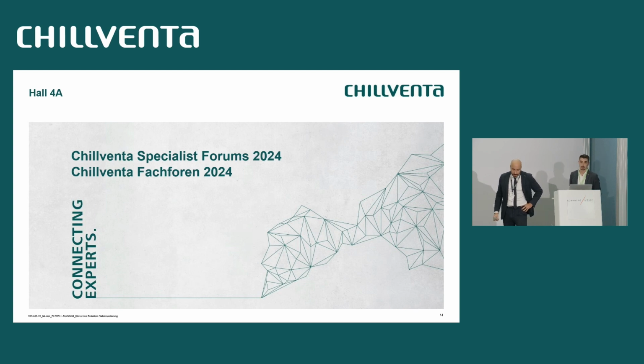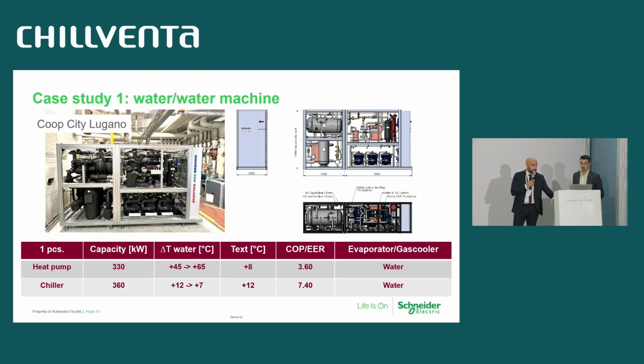Does it provide heating and domestic water? Yeah, not in all the projects, but for example, in the last one in Lugano, we provide both hot water and space heating water at quite the same level. So, for example, space heating water temperature required is around 60 degrees, and hot water requirement is obviously higher, up to 65 degrees.